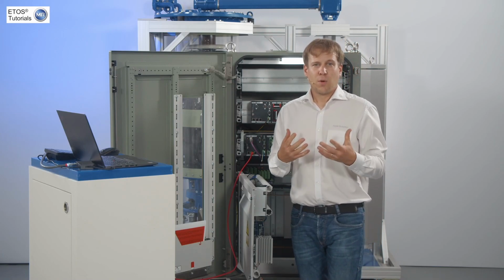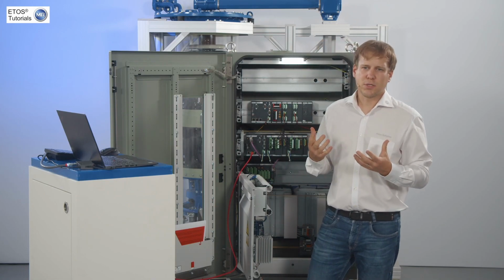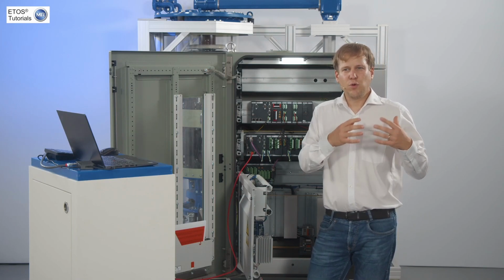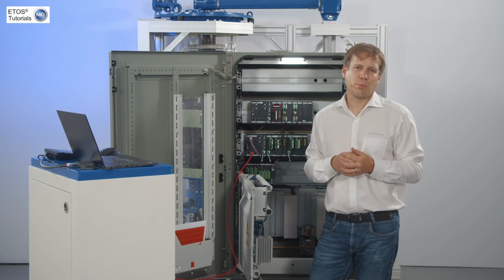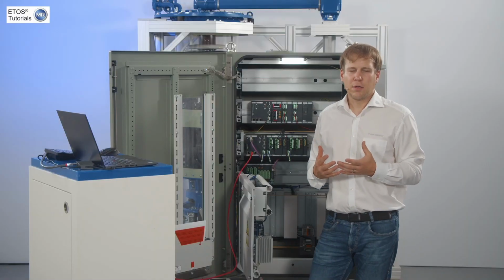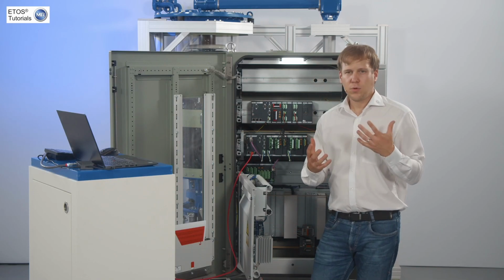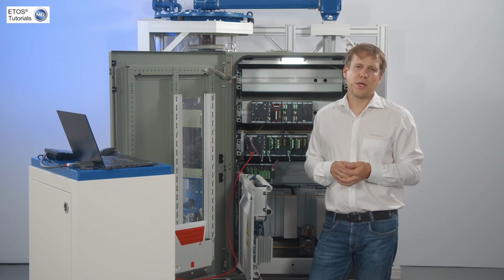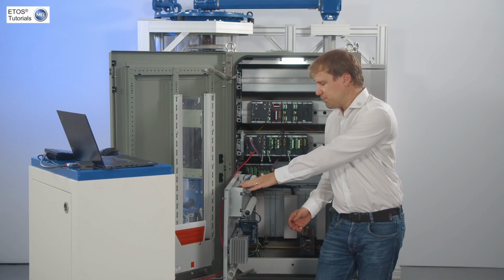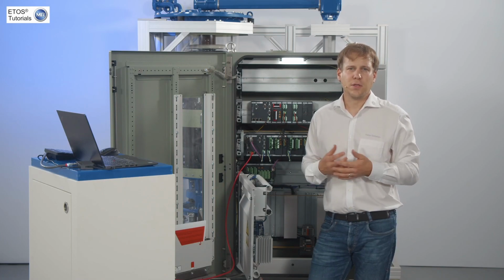Number four, quite often, if it's a larger setup, the DIO module has its own power supply unit. Quite often we had the case that customers forgot to connect or to power up that additional power supply unit. In this case, the LEDs of the DIO module would remain dark. It's very easy to spot that, and then you can check through the diagram to see if the correct power supply unit is powered up. Also, the power supply unit here in the frame, maybe you can see it, has a little LED on top that gives you indication that everything is right and the unit is up and running.